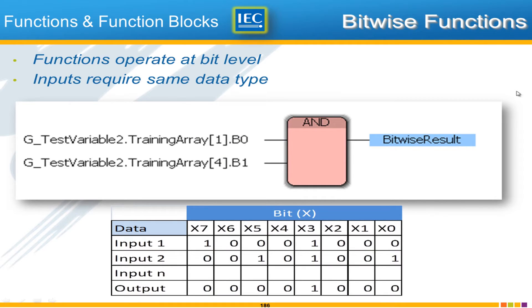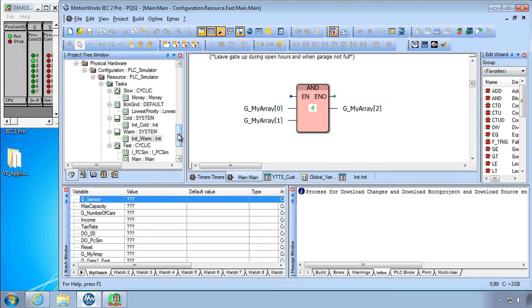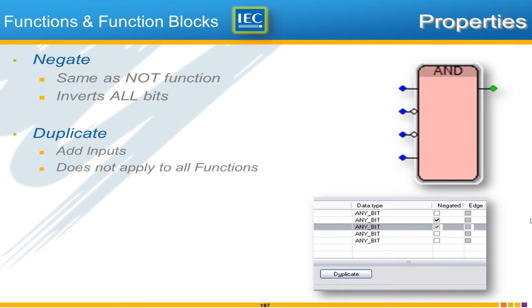When working with functions, some have what we call a bitwise operation: given two inputs of the same data type and a block such as AND or OR, the bits of that data are ANDed. This is more than just two ladder contacts in series because you're not limited to using only Booleans. You can use any data type and the data is ANDed with a bitwise result — if Input1 has certain bit values and Input2 has other values, ANDing means combining them bit by bit to get the result.